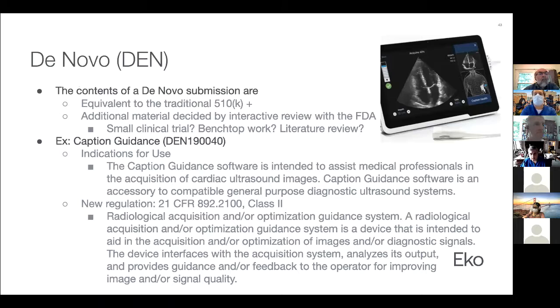There's a really interesting question in chat, Dr. Saltman, about whether arguing a predicate substantial equivalence might be viewed by, let's say, patent law as not novel. So yes and no. Totally depends on the situation. So for example, with our Duo device, there's no device on the market that both picks up sound and electrical signals. So this is quite novel, right? I didn't have to do a de novo because we were able to make the argument to the FDA that there were 2 predicates, we were substantially equivalent to both of them, and we were fine. On the other hand, you could make just another stethoscope. If you want to make it cheaper or better or whatever, doesn't have different technological characteristics, the FDA is okay with that. That's a good predicate. But you know, you might want to be an also ran for half price, and so you take over the market as a commodity. That's done too. So the answer is it depends.